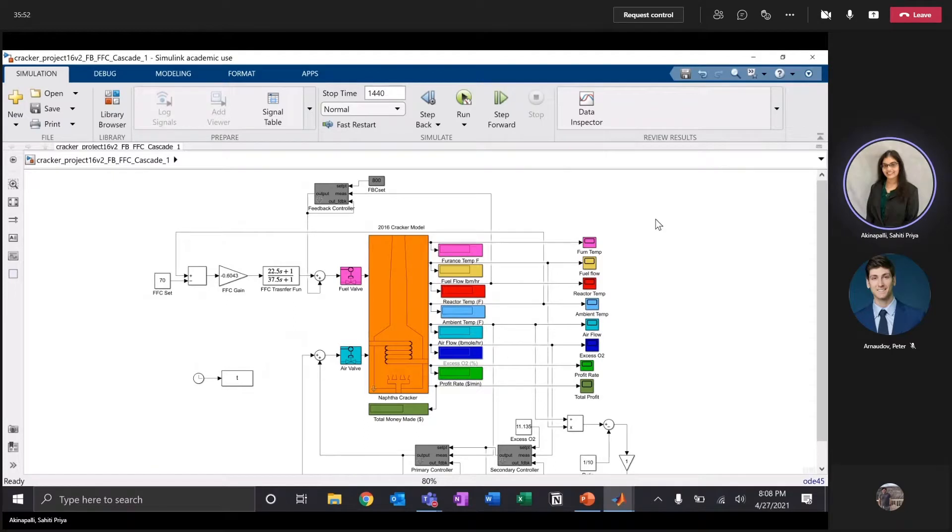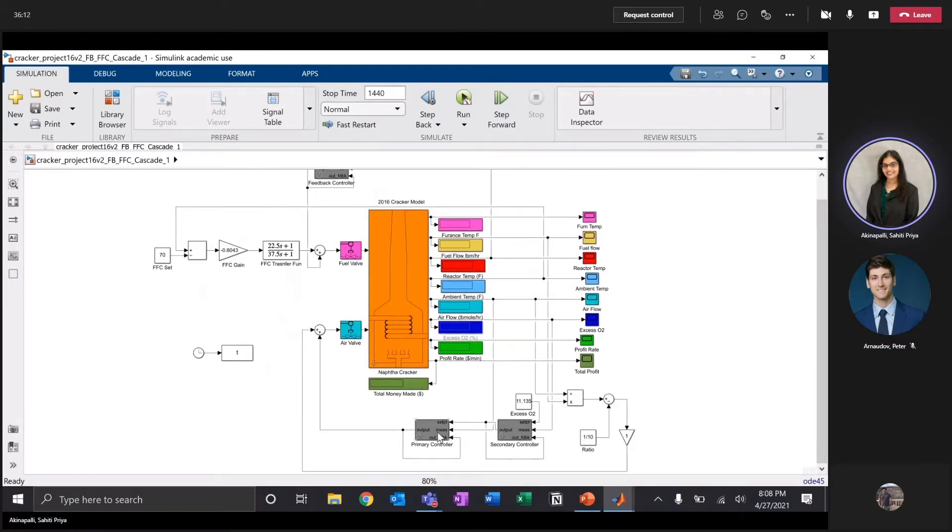Here is the control scheme for the naphtha cracker process. First, there is a feedback controller from the reactor temperature to the fuel valve. Then, there is a feedforward controller to control the ambient temperature by adjusting the fuel valve. Further down, there is a cascade control loop, which controls the air valve based on the excess O2 and air flow, followed by a ratio control, which also adjusts the air valve based on the flow of fuel and flow of air.